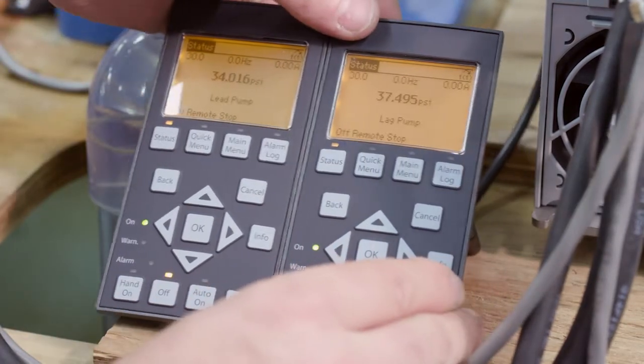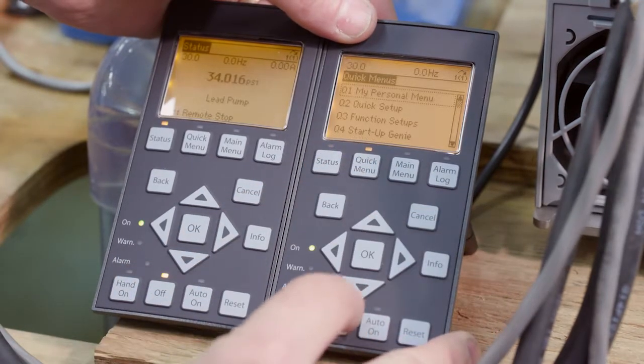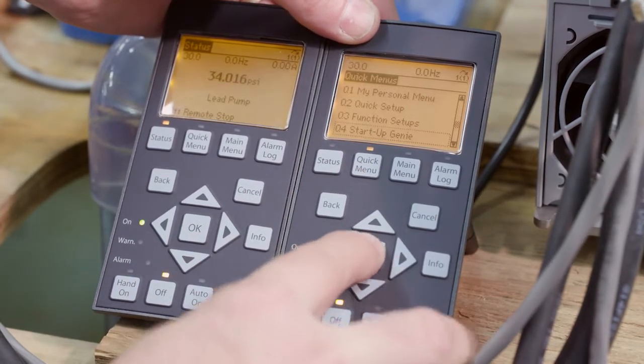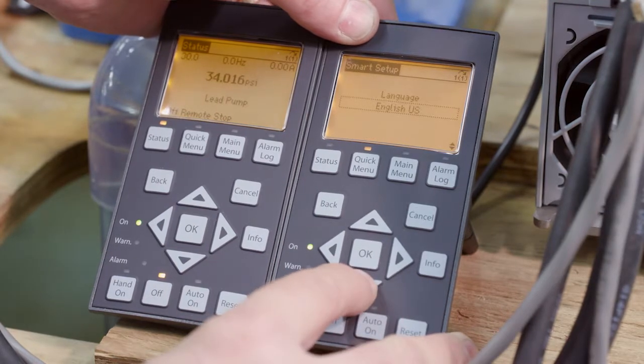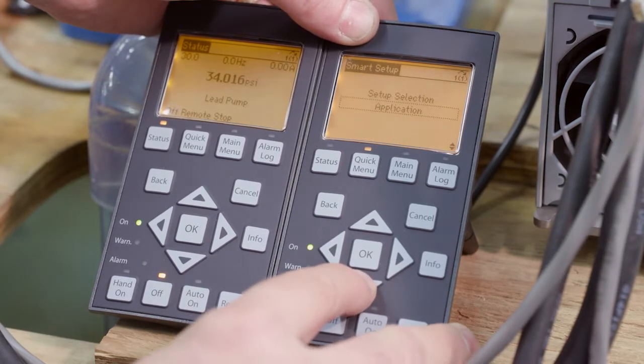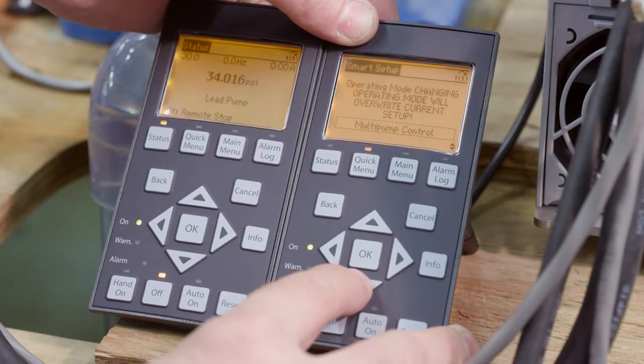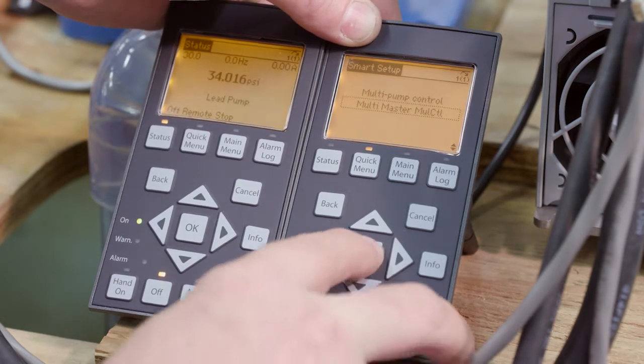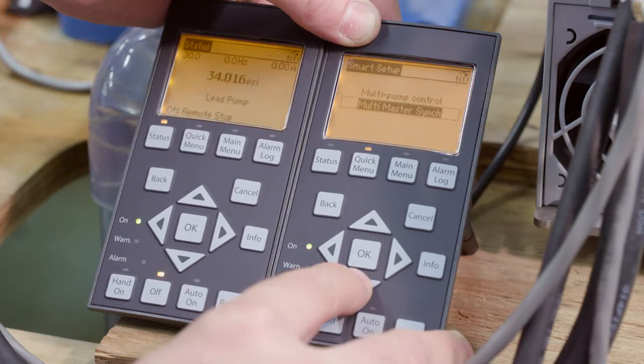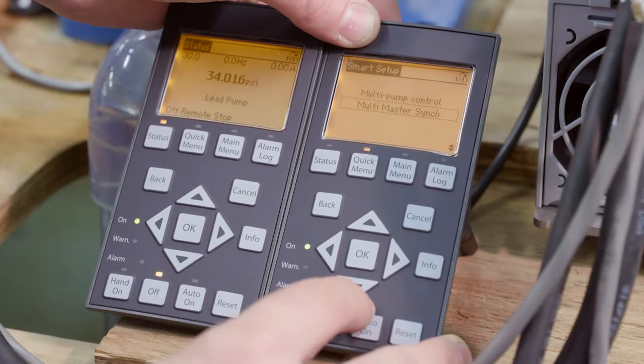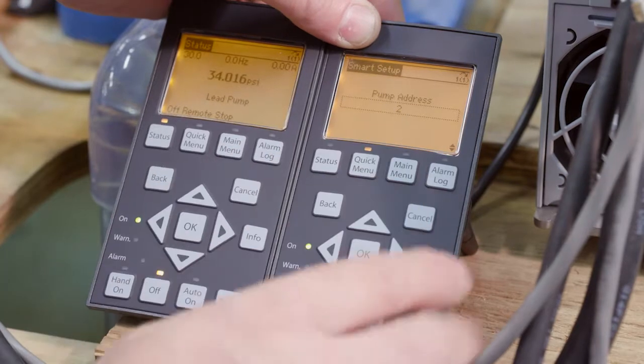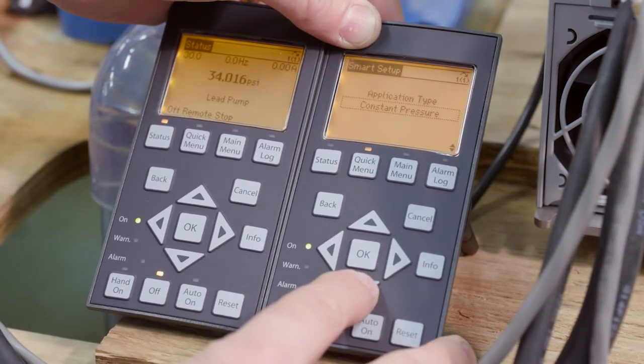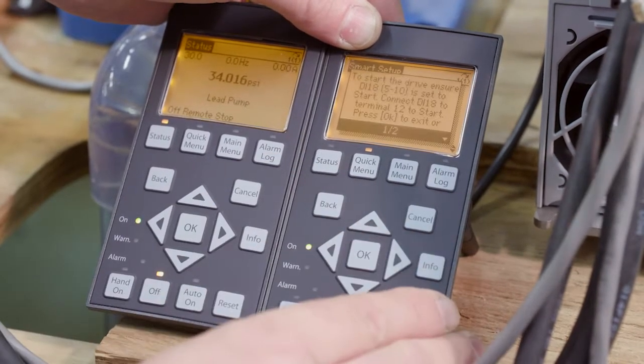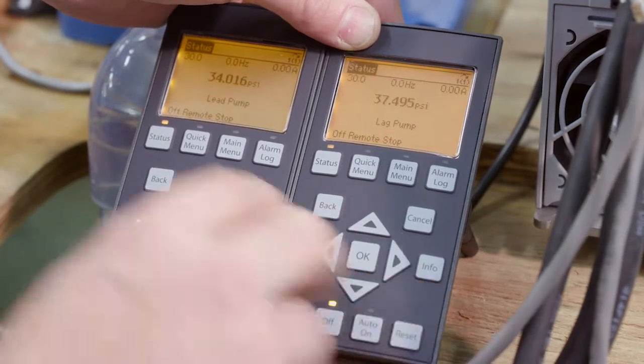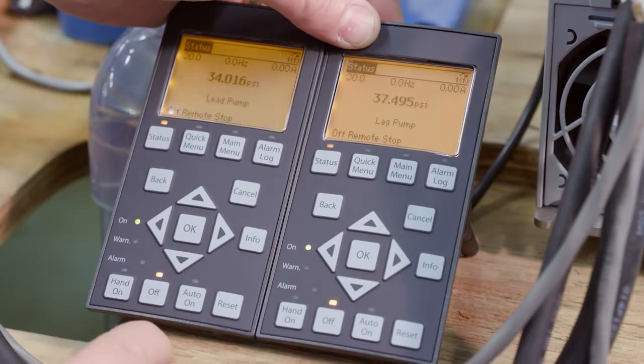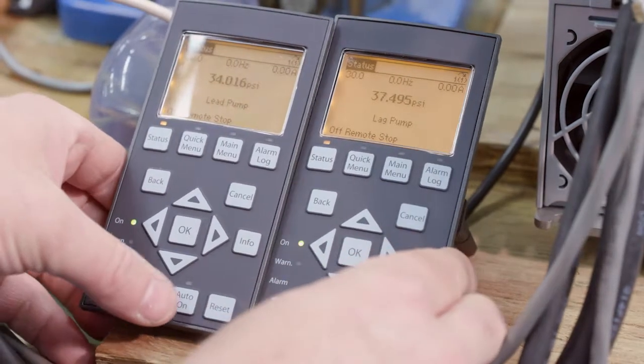Now let's go to the lag pump here, same thing. Startup Genie. So multi-pump control. Let's change that to multi-master Synchronous. And we still have pump address 2. Let's go back, hit the status button. So we still have my lead lag. Now let's hit the auto on.